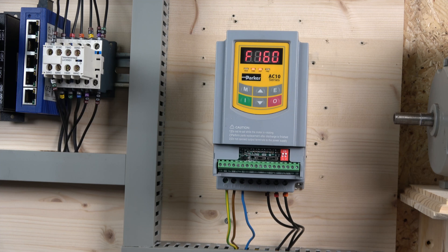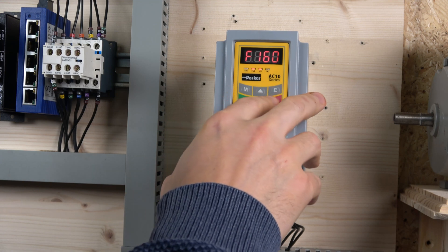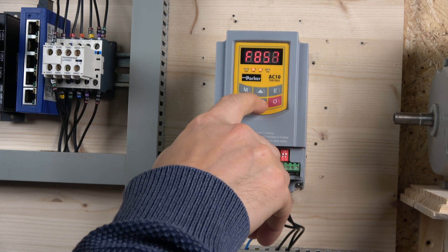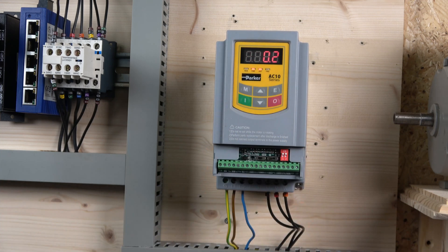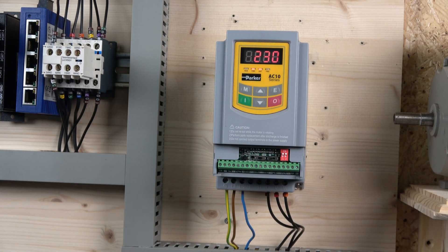Next up are the motor parameters. Go to group 800. Parameter 801 is your kilowatt rating — in my case it's 0.18 kW, so I'll set it to the closest value of 0.2. The next parameter is motor rated voltage. I'm running a single-phase motor at 230 volts, so I'll set 230 volts — depending on your country and what voltages you operate with.